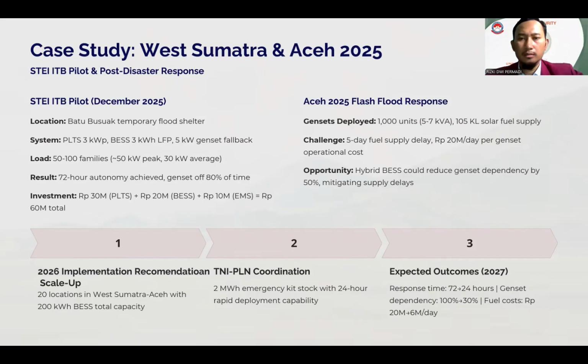I will continue the presentation about the case study West Sumatra and Aceh 2025, STEI ITB pilot and post-disaster response. The STEI ITB pilot in December 2025 was located in the Batu Busuak temporary flood shelter. The system is PLTS, BESS, and genset fallback. Load is around 50 until 100 families. The result is 72-hour autonomy achieved, with genset off 80% of the time. The investment is 30 billion rupiah for PLTS, 20 billion for BESS, and 10 billion for EMS, so the total is 60 billion.